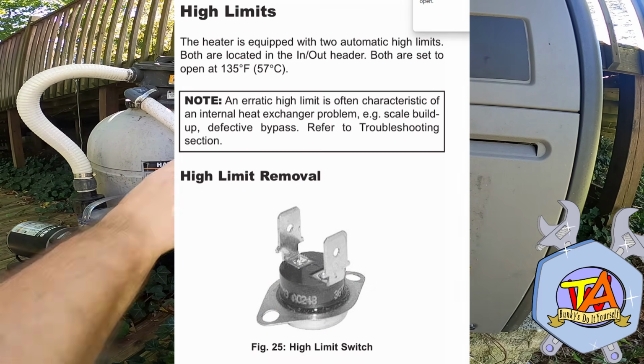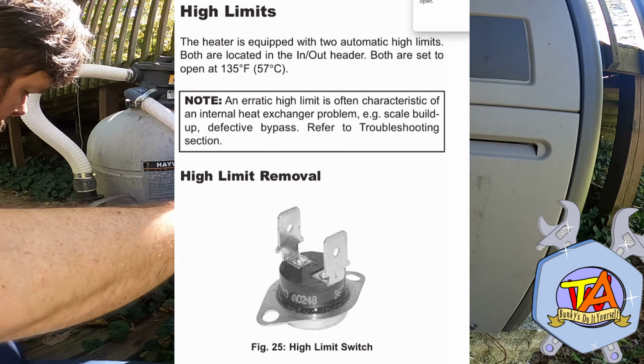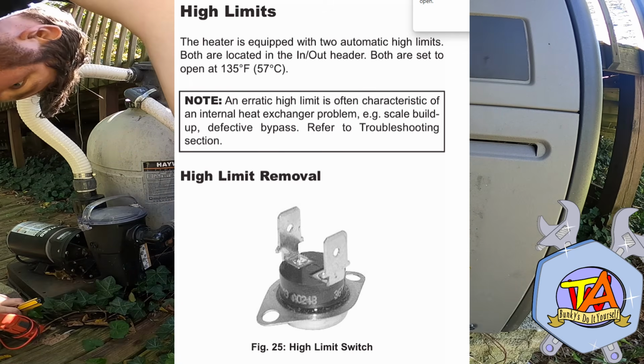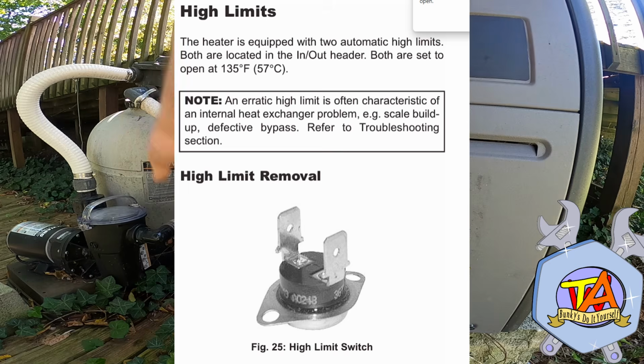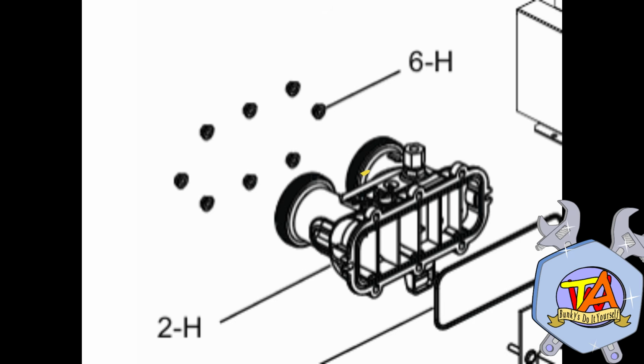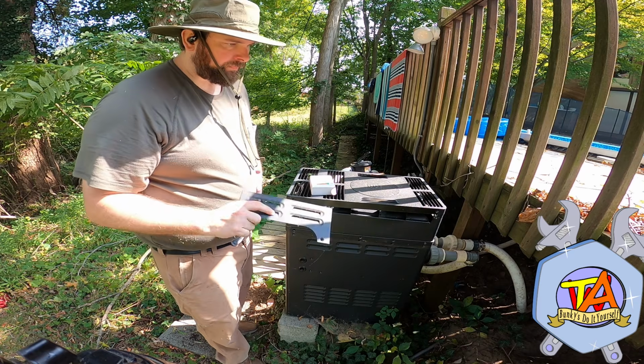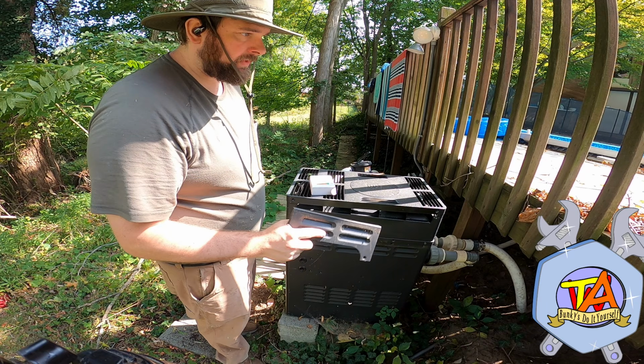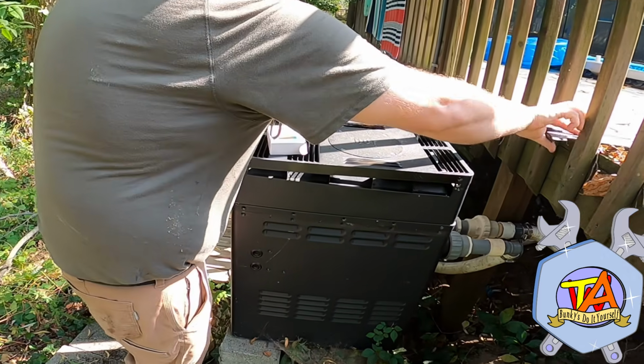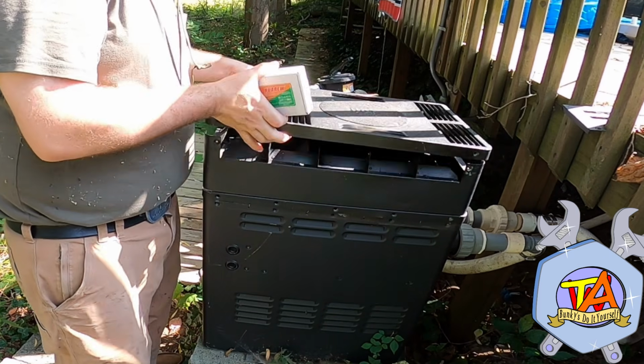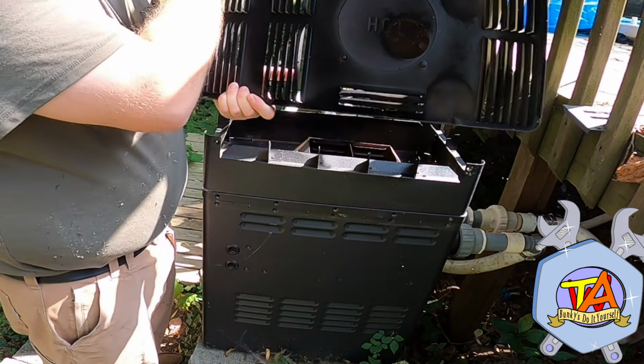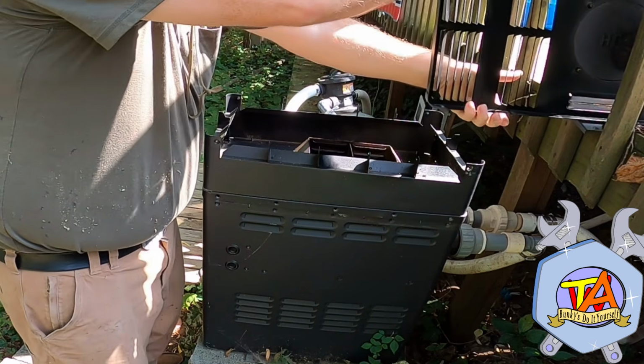So there are also 2 high limit switches that can go bad that are set to 135. They are located on the inlet and outlet. There's a small panel in the back that you are able to access these without removing the whole upper unit. But since I need to clean all the bug guts off of this thing, I'm going to go ahead and access them and test them out.